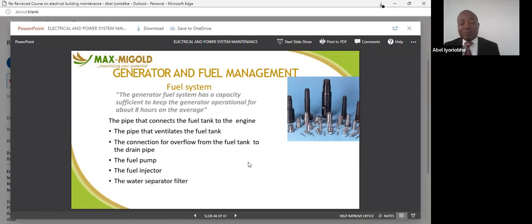This means you need to pay adequate attention to the fuel your generator uses, and ensure the elements that allow fuel to flow from one point to another are well cleaned — just as you'd ensure your heart or vessel is clean. Whatever fuel they bring to your site, you start your checks from there. That's why you need to carry out tests before accepting your diesel.